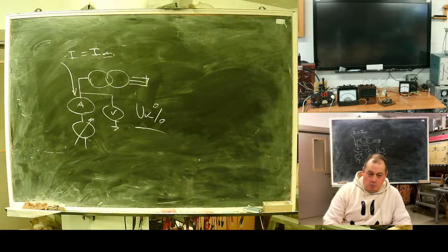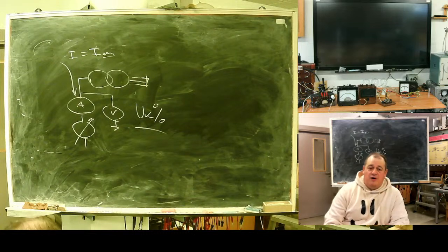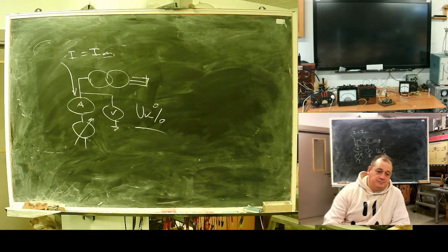Actually, for most large transformers you will see something between 10 and 11%. For some small ones, you may find 5. But in relative values, this voltage does not go far. Good.